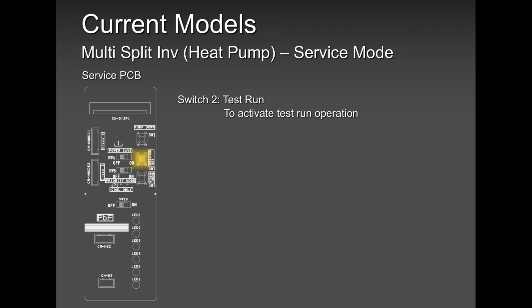Everybody tells me test run is good when I'm done with my job. When I finish the job, my vacuuming, everything is ready, release the gas, test run, I put the unit in test run. Well, test run is not a bad idea to do after you finish your job, but if you have crossed the wires, that's a bad idea. Because in test run, if you have crossed the wires, when I say crossed wires, I mean unit A wiring went to unit B. It has happened in the past, it has happened to you who are listening today, and it will happen to you again in the future. So that test run will not find that fault.